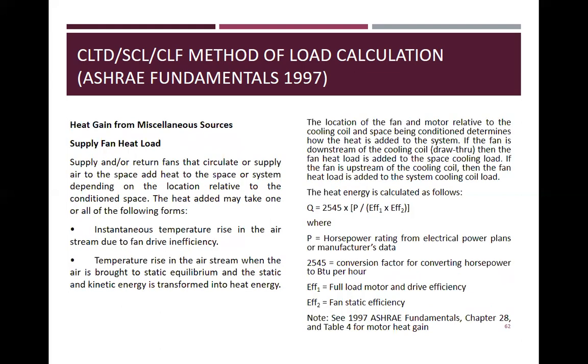Now, heat gain from miscellaneous sources. We have the supply fan heat load. A supply fan or return fan that circulates or supplies air to the space adds heat to the space or system, depending on the location relative to the conditioned space. The heat added may take one or all of the following forms: instantaneous temperature rise in the airstream due to fan drive inefficiency, then temperature rise in the airstream when the air is brought to static equilibrium and the static and kinetic energy is transformed into heat energy.